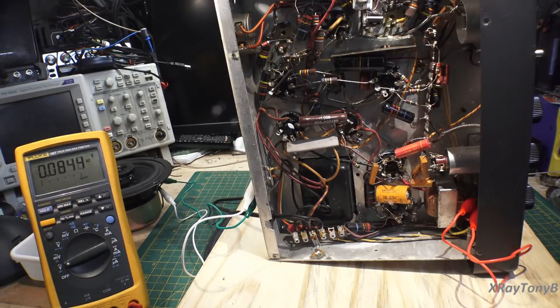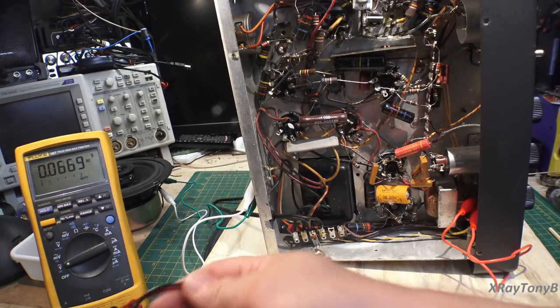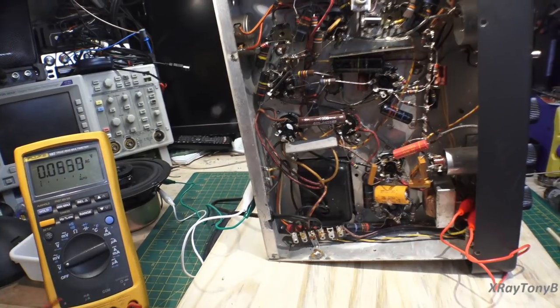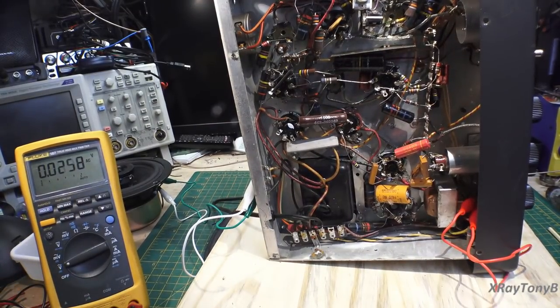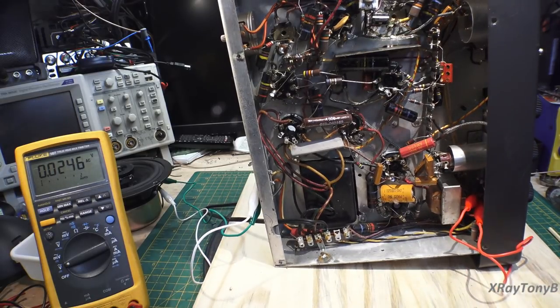I'm going to turn this down because I don't want to push the issue with this pink capacitor. I was getting just a teeny bit of current, showing that those filaments are lit up and drawing some current. So we already know we have a good transformer to work with, but we do have a bad switch. Now that we know that's good, we're going to take a few other measurements before we hook up any high voltage.